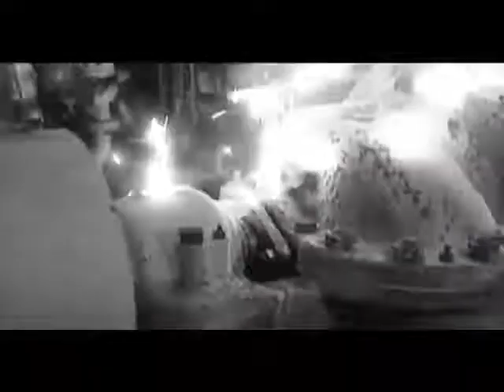Due to the pump's design and a lack of communication, the night crew didn't realize the extent to which Line A had been disabled. When the Line A pump was repressurized, gas at 1100 psi shot out of the valve with a deafening shriek. So eventually, this layer of condensate gas, which now, of course, has become mixed with oxygen and is only looking for an ignition source, finds the ignition source. What that source was may never be known. But at 10 o'clock, a giant fireball ripped through the condenser module and destroyed the control room.